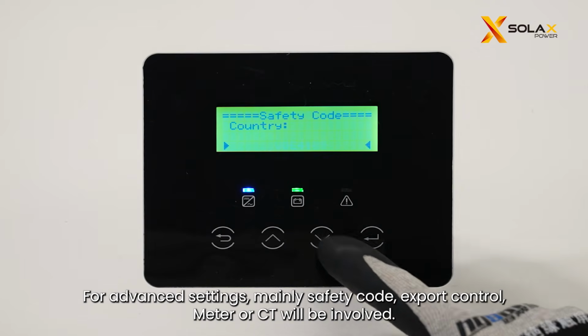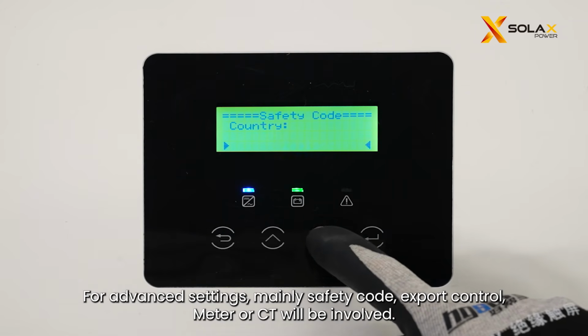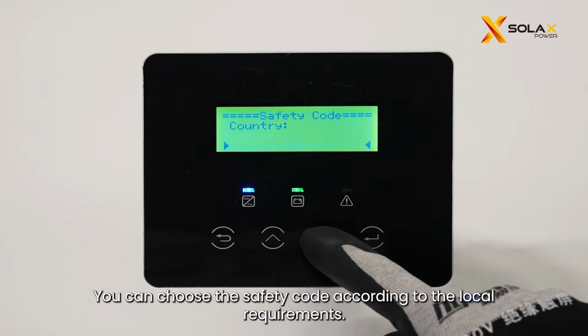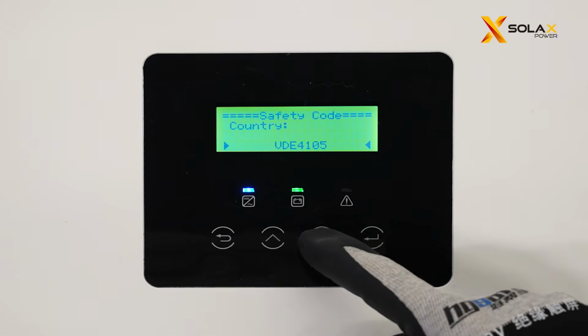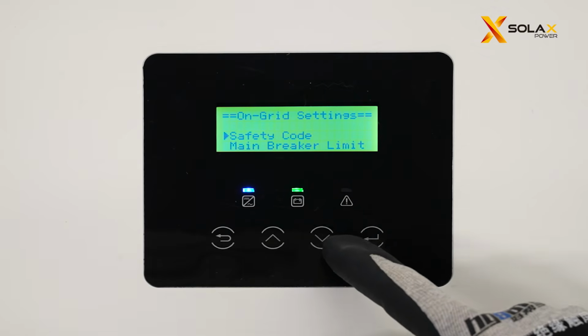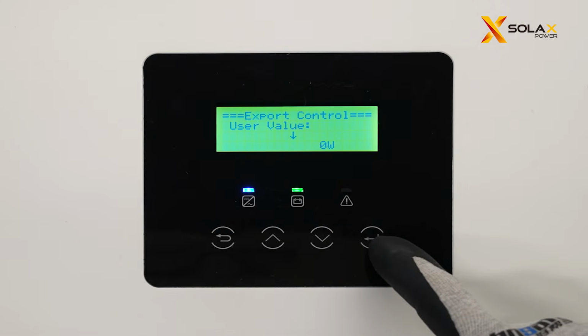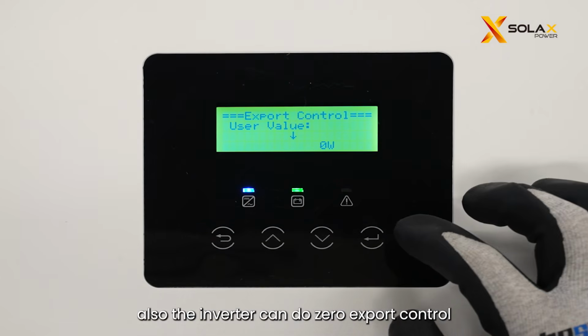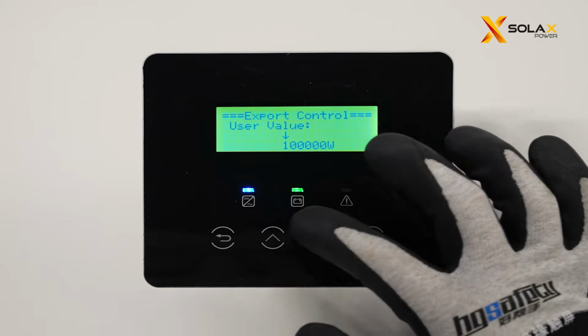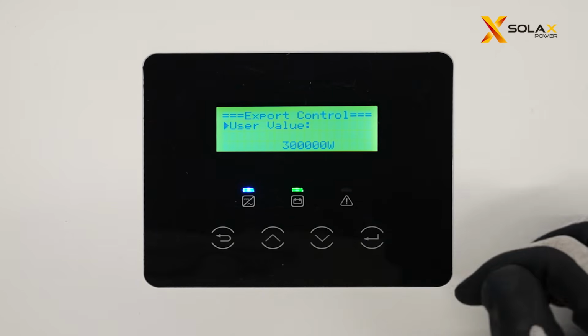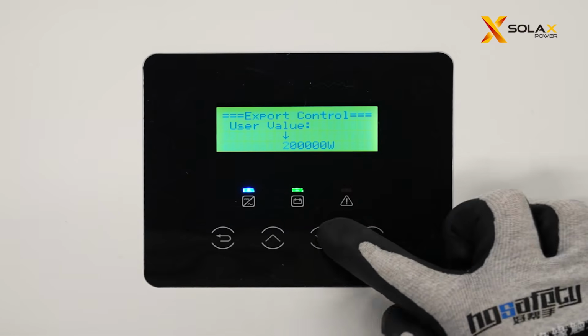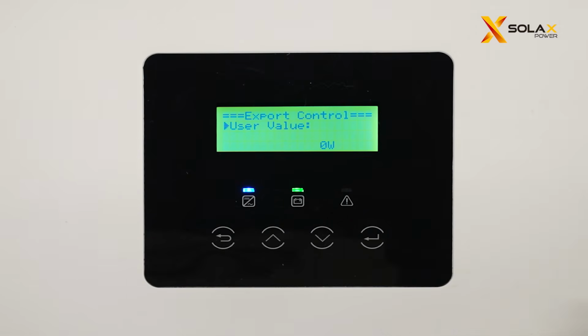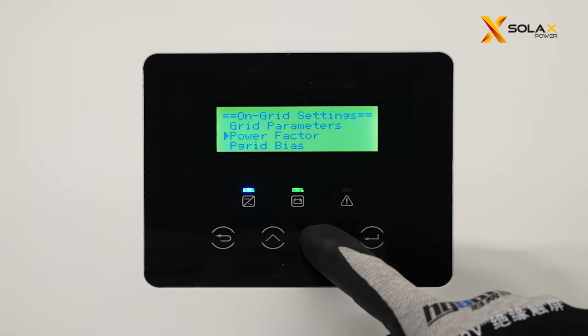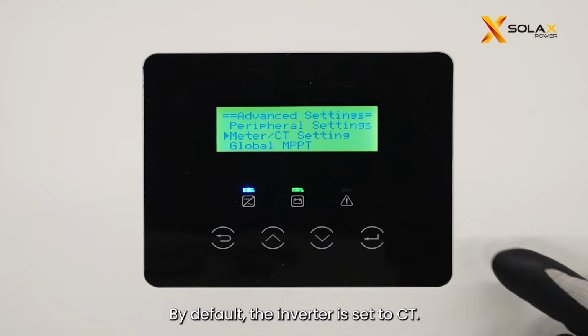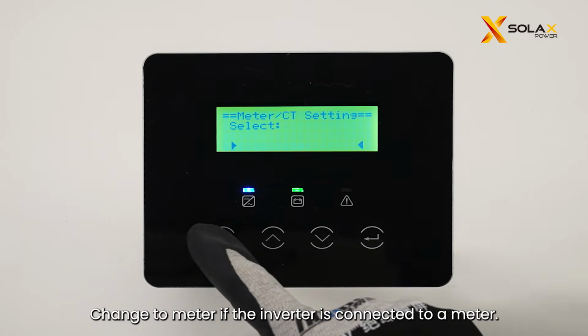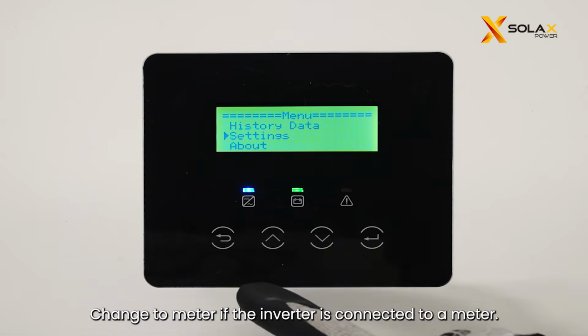For advanced settings, mainly safety code, export control, meter or CT will be involved. You can choose the safety code according to the local requirements. Also, the inverter can do zero export control. By default, the inverter is set to CT. Change to meter if the inverter is connected to a meter.